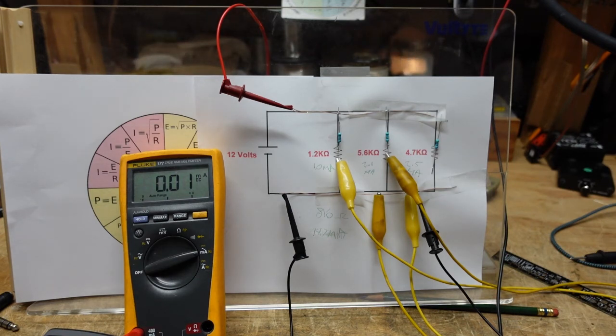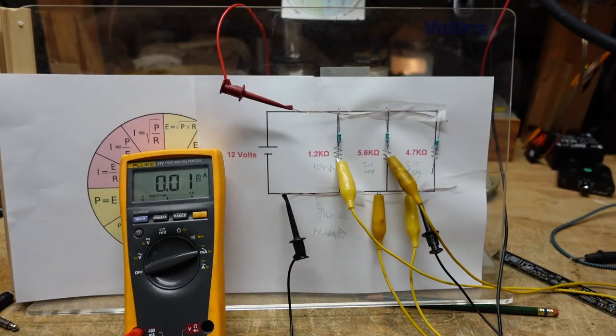These are things you want to have an understanding of. There are times when we're troubleshooting where we need to calculate what our voltage or current might be. As I said before, we may have a resistor that's burning up, we want to know why. So we can calculate how much current is going through and then we can calculate the power. If it's a quarter watt, half watt, one watt resistor we can see if we're above or below that. This is a useful skill to have.